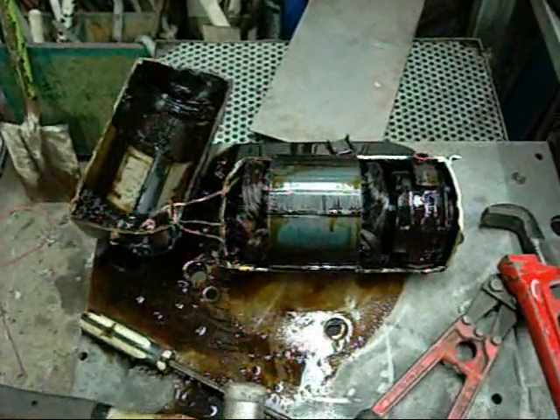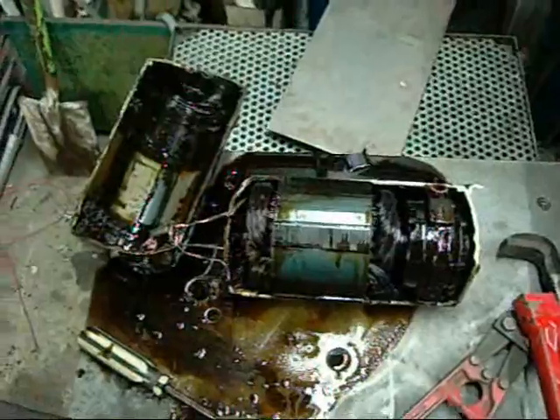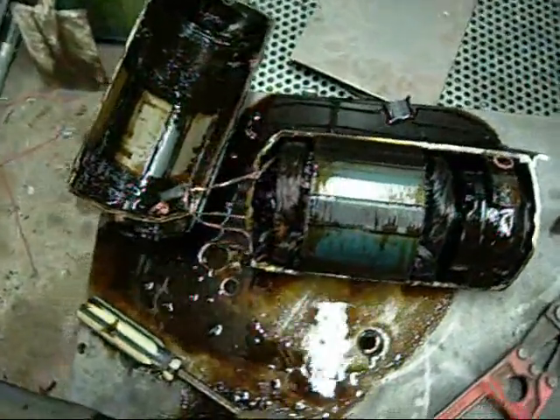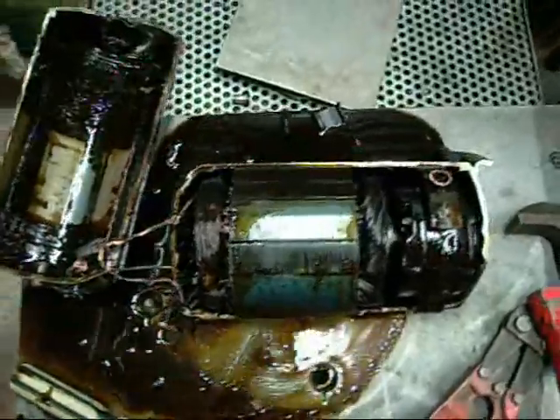This is the compressor from the Taiwanese condensing unit that I tortured the other day. The oil sort of looks like engine oil — it's burnt. It stinks inside, and these wires are all burnt up.